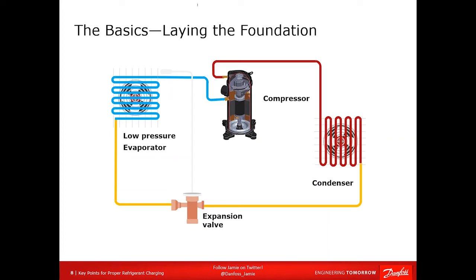Here is a basic system. When you first start technical school in HVACR, they show you this four-component diagram: an expansion valve, an evaporator, a compressor, and a condenser. The low pressure, low temperature side designed to absorb heat is on the left. The high temperature, high pressure side designed to reject that heat — plus the work the compressor adds — is on the right. The expansion valve maintains that pressure difference and meters refrigerant at the correct pressure, temperature, and amount based on the load.